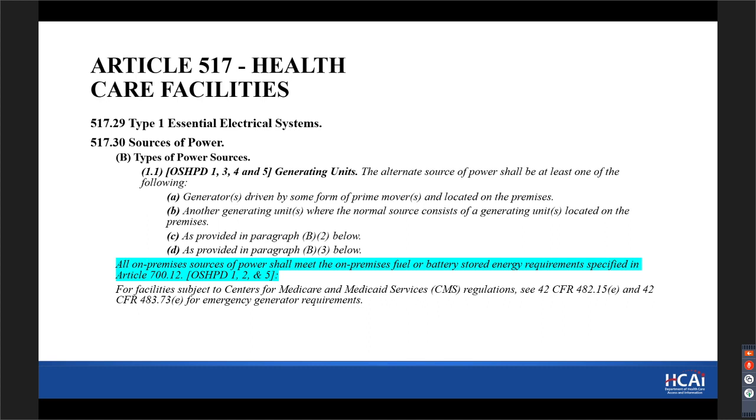Surgery centers in MOBs, we'll find, and lots of discussion, there is a new law, new PIN 74, which increases the requirement for on-site fuel storage or provisions for operation of on-site emergency power generators for SNFs. And then we just have a pointer down here about, in order to meet CMS requirements, you do need to have a generator for your emergency source.